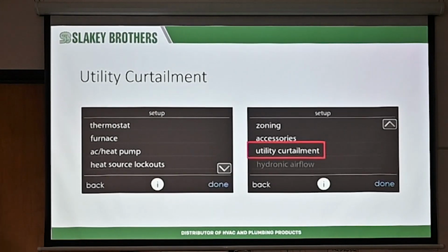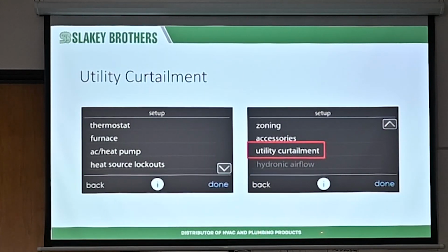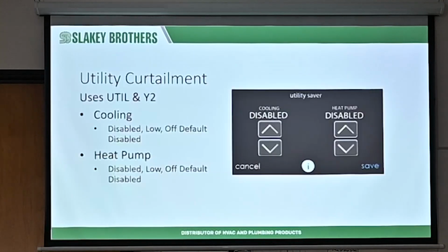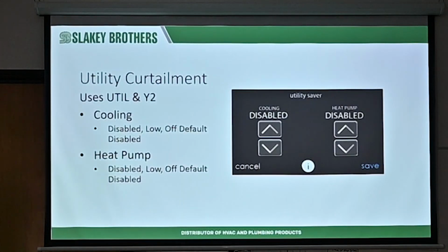Utility curtailment. Do you guys have service interrupters up here, where they're rolling blackouts and they shut down the condenser at times? Okay, no. That is an option there. It's an Evolution system. So again, just like a safety, we don't want to cut the communication line. We don't want to cut the low voltage or anything like that. But we want the outdoor unit to shut off with the utility curtailment, basically.